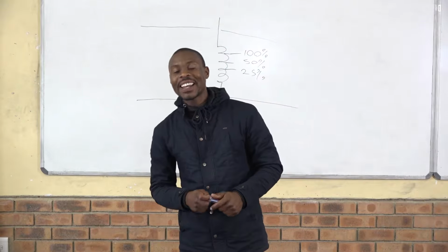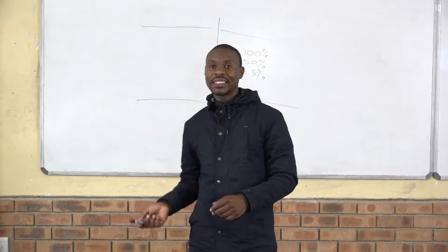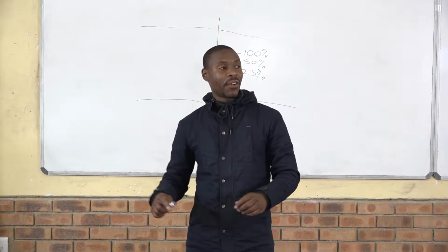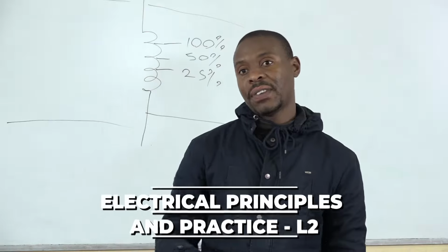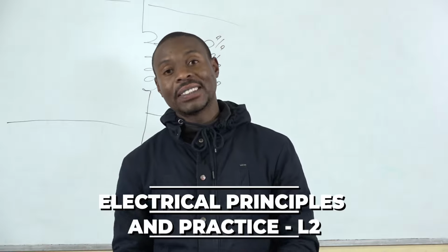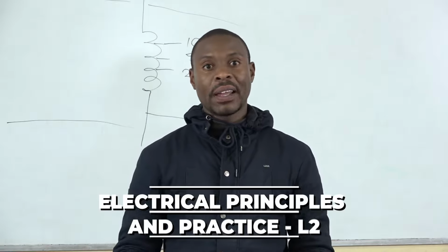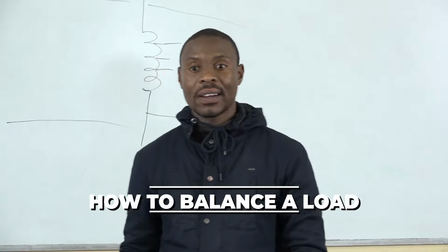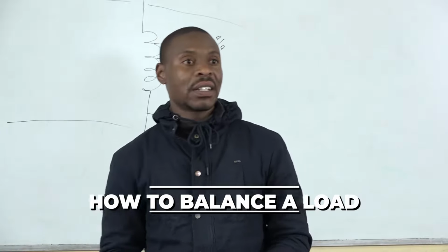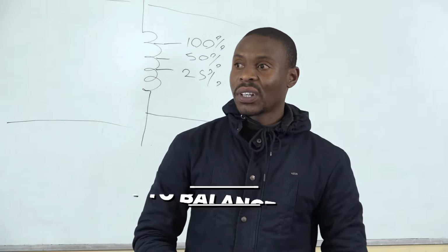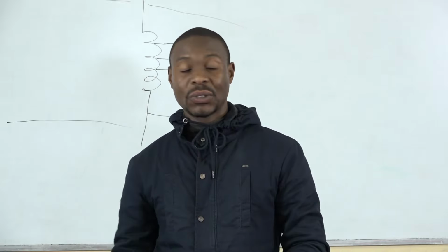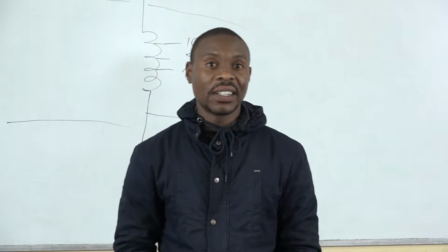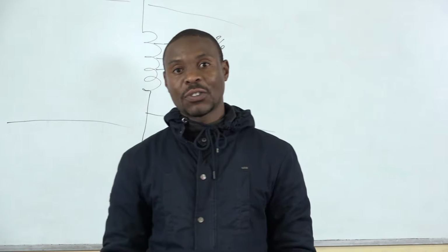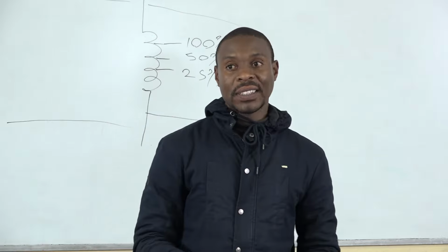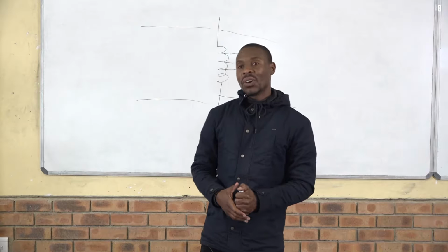Okay, students, to summarize what we have done from load balancing to transformers. For load balancing, we said we must have a 3-phase 4-wire system, then you have to balance your load, by making sure that each and every line or phase is taking an equal share. And then we said you must also do the calculations to make sure that you don't exceed the transformer rating, because we are balancing it so that the transformer cannot explode. We went again to transformers. We do all the calculations.